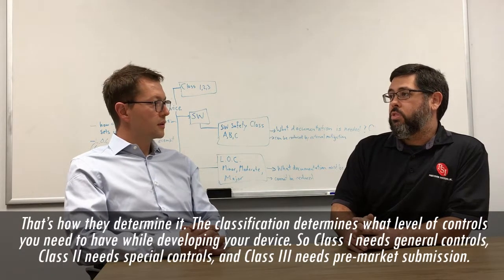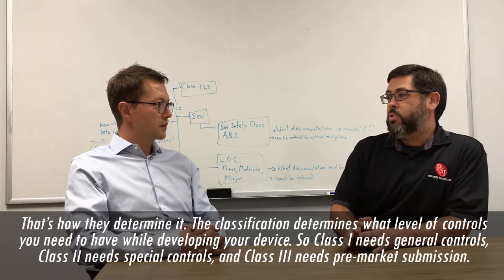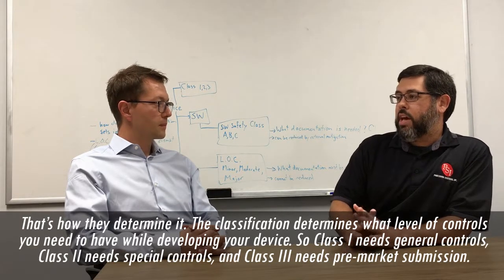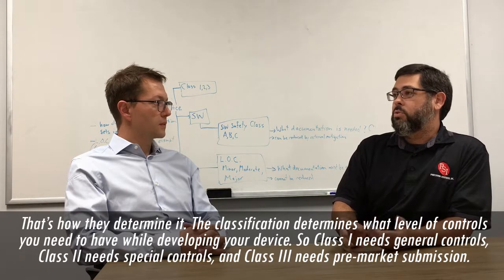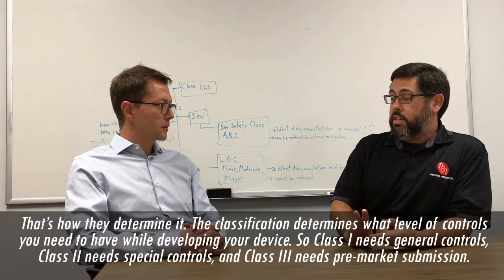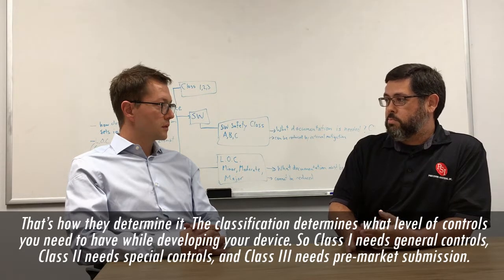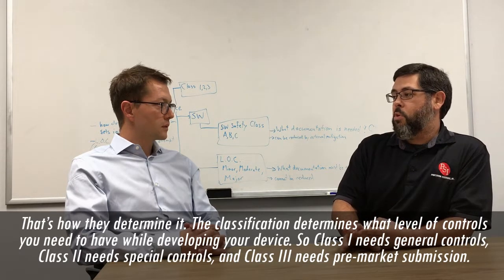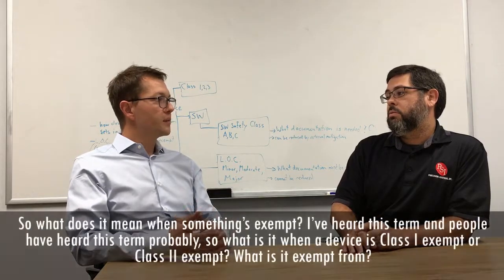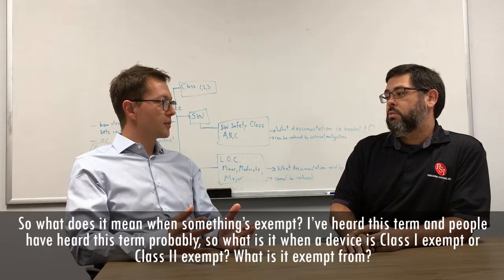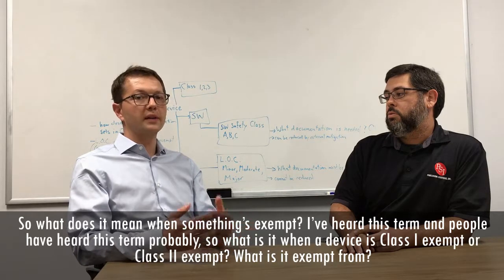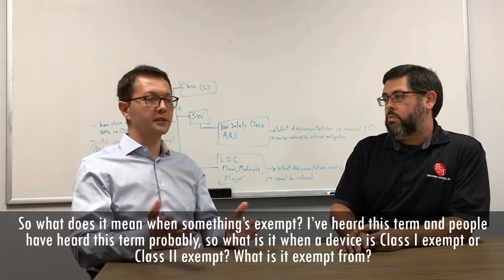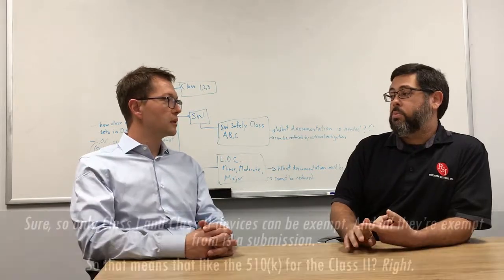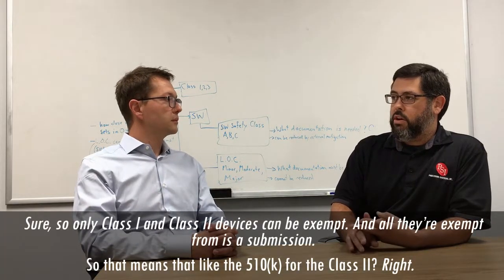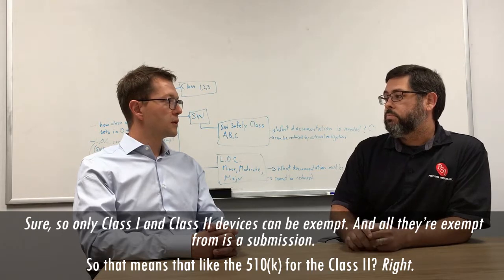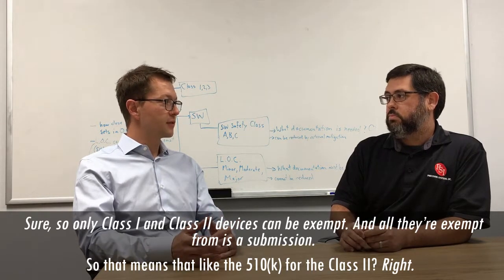Okay. The classification determines what level of controls you need to have while you're developing your device. So class 1 needs general controls, class 2 needs special controls, and class 3 needs pre-market submission. So what does it mean when something's exempt? I've heard this term, and people have probably heard this term. What is it when a device is class 1 exempt or class 2 exempt? What is it exempt from? Sure. So only class 1 and class 2 devices can be exempt, and all they're exempt from is a submission.